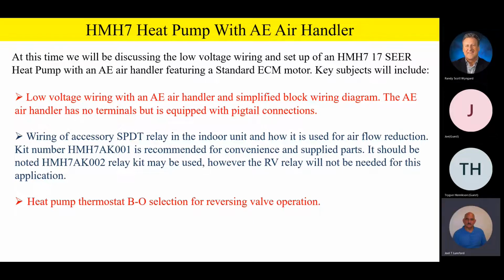Now we're going to recommend kit number HMH7AK001. We recommend this because it's very convenient and it has all the supplied parts for the unit. That kit contains the relay, a little wiring harness of field supplied wires, as well as a bi-flow filter dryer. This is the only product we have in our inventory that does not have a factory installed filter dryer, but we do provide one in this HMH7AK001 kit, along with the relay and so on. So we recommend that you buy the kit for convenience.